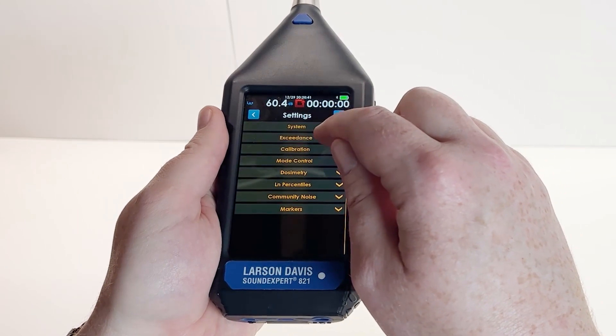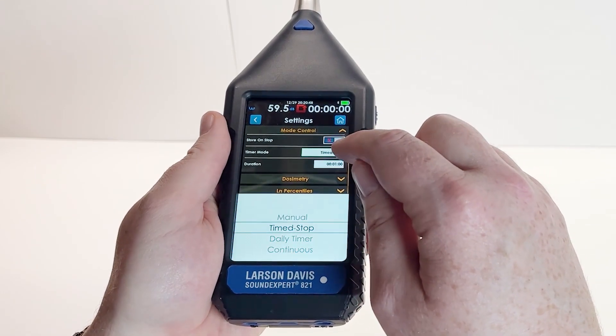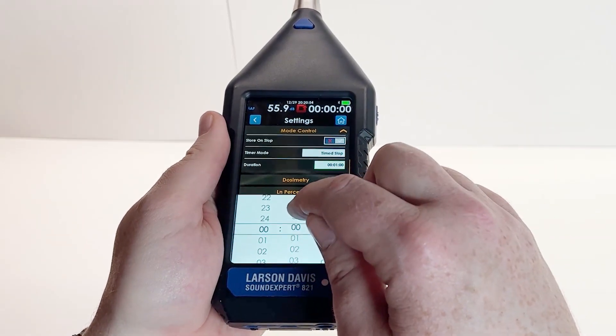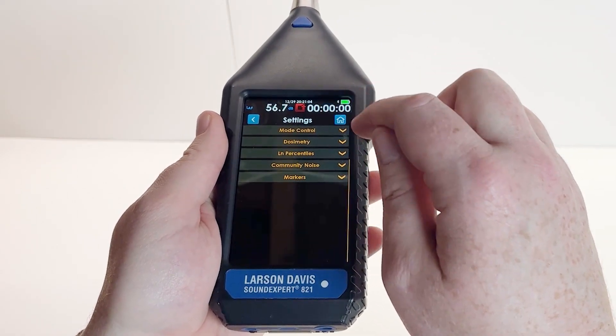Now we're going to go into the mode control. We're going to disable store on stop by tapping on the X and checkmark toggle. Now we're going to enable the timed stop feature to make each individual metric the same duration. This is not required, but it is recommended. In our example, we're going to set this to one minute. This is all that is needed to configure the 821 to conduct a site survey.